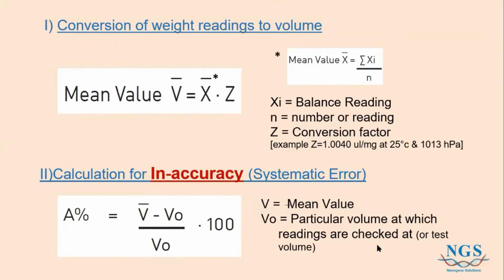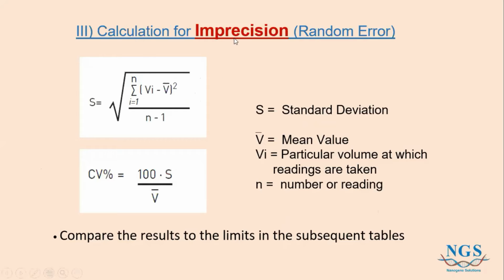All right, so let's move on to the next calculation, which is imprecision. That's also known as random error. It's different from a systematic error, also known as inaccuracy, because it's an error that you really cannot predict. It can be because of your technique, or because of your environment. It's something that you cannot blame on the pipette, but you can always look into your technique and your environment to solve this. Also very straightforward, you want to find the standard deviation first for each checking volume. Then you follow up with the imprecision formula, which is CV percentage: 100 times the standard deviation that you found, divided by the mean value. You do this 3 times, once for each checking volume.